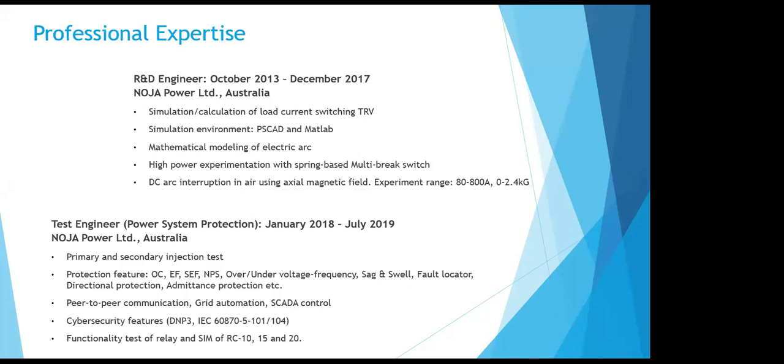During my PhD, my work was mostly focused on arcing experimentation. The primary work was simulation of load current switching transient recovery voltage, basically the electrical stress created by the network when an interruption happens inside a switchgear.